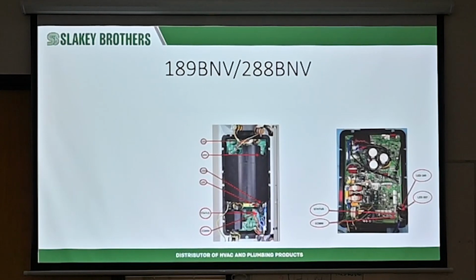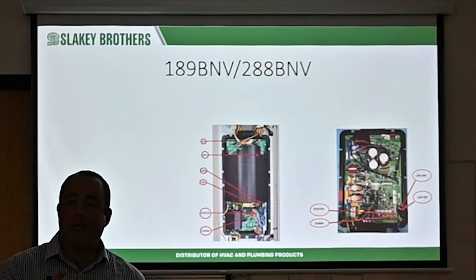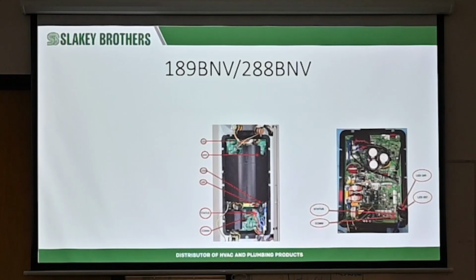But when you look at anything, they're all so damn similar. Every one of them works the exact same way for air conditioning or heating. You're basically removing heat from one space and tossing it somewhere else. Air conditioning takes heat from here and puts it out there. A heat pump in heating takes heat from out there and puts it in here. Refrigerant does the same thing. A compressor does the exact same work. It still takes refrigerant, compresses it, the refrigerant changes states, fans move the air indoors and outdoors, and so on. They all have metering devices. Electronic ones still regulate the refrigerant. I can still look at refrigerant, I can still look at flow, I can still look at all that.